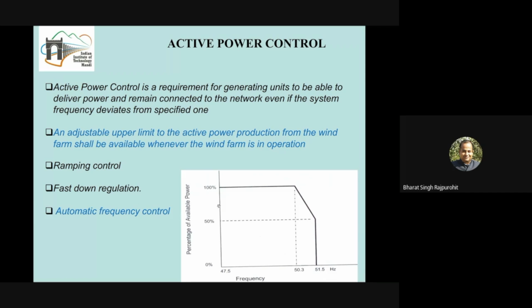But is it possible to increase the output from a wind turbine? We see that it is not possible. The reason is that we are already working on maximum power point tracking. Whatever maximum power is available, we are always using, working at that point. If suddenly the grid is asking for an increase in output because the frequency is low, we are not able to increase it, because we are always working on maximum power point tracking to extract the maximum amount of energy. So participation in supporting a lower grid frequency by increasing the power output from the wind turbine is not possible.